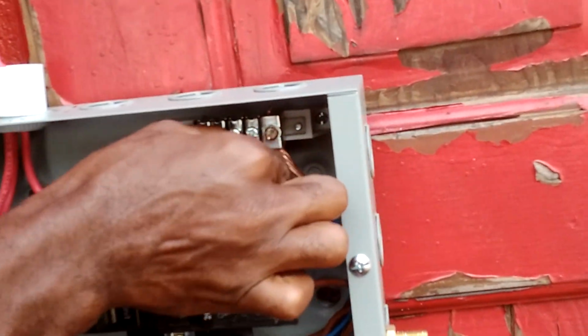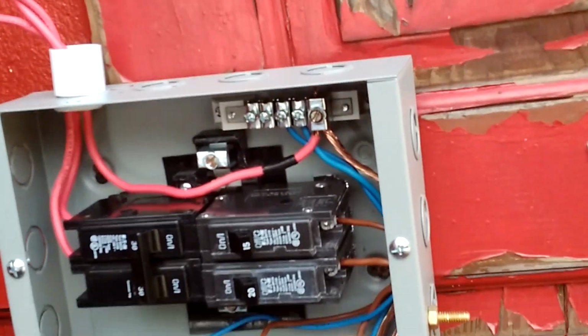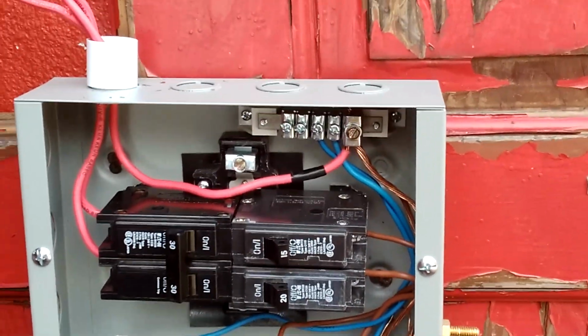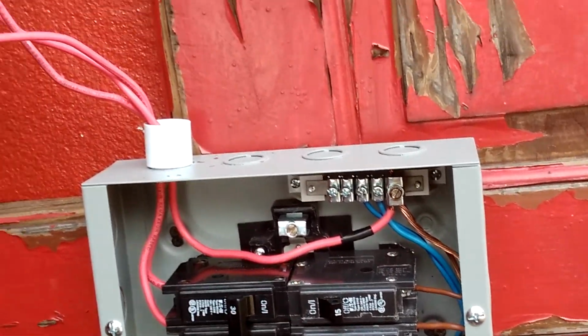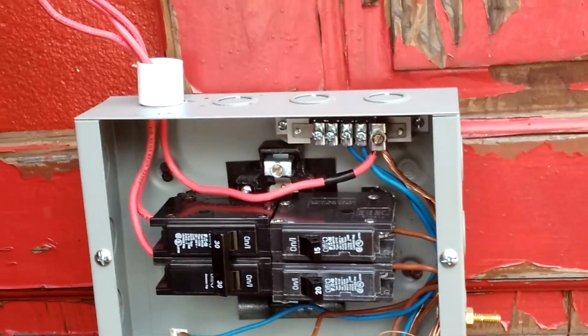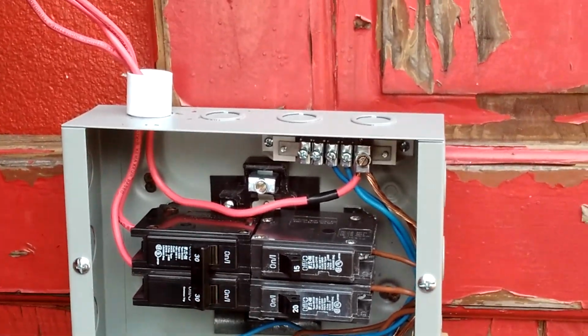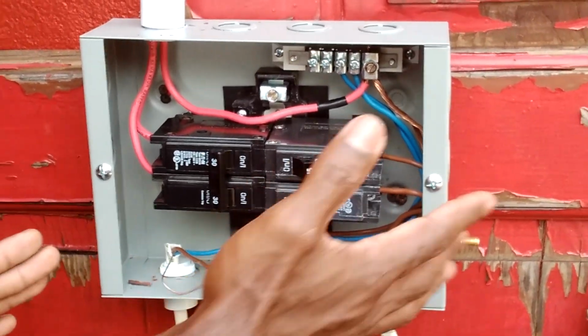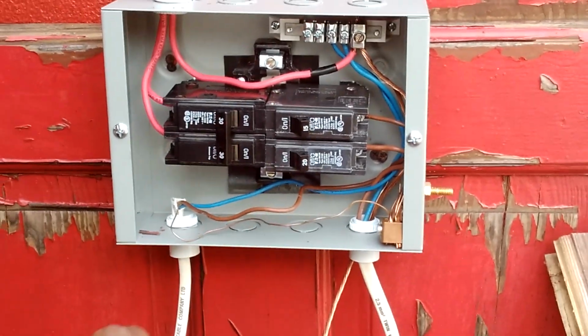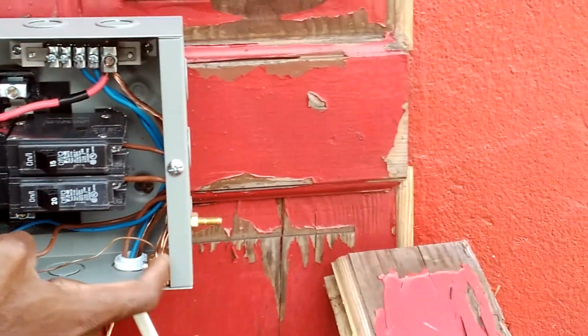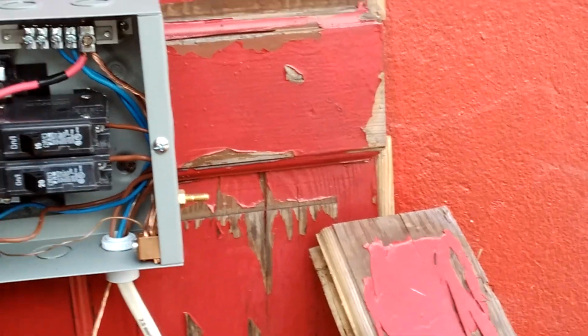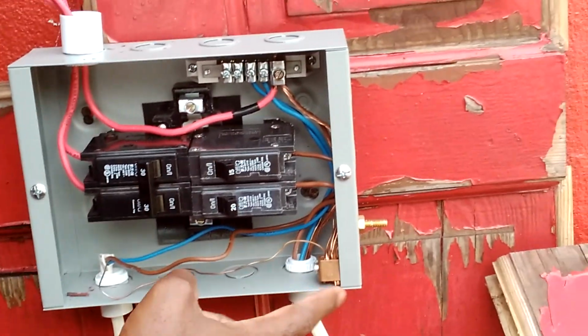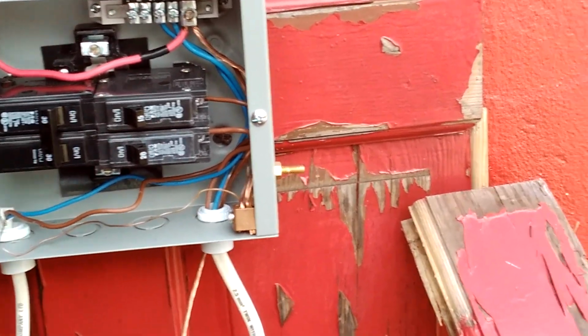I just want to make sure it's nice and tight - remember, no loose connections around here. As I said before, this earth wire normally goes to your earth rod driven into the ground for protection of the circuit. It goes to the neutral bar first, then it's linked to the earth lug, and all other earths within the circuit are linked to this earth lug here.